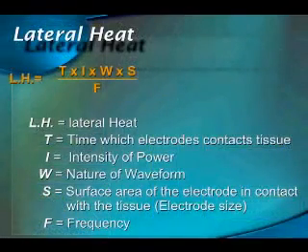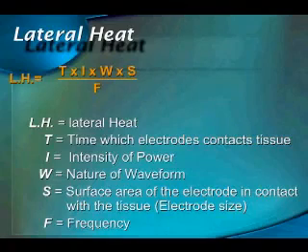The key to the advantages of radiosurgery and its most efficient use is summarized by the concept of lateral heat spread. Using swift light strokes to minimize time of tissue contact and using a low power setting on the cutting mode will yield clean cutaneous incisions without impeding wound healing. Higher power settings and the use of the rectified waveform blended cutting and coagulation mode can be used without untoward effects when resecting orbicularis muscle or orbital fat.